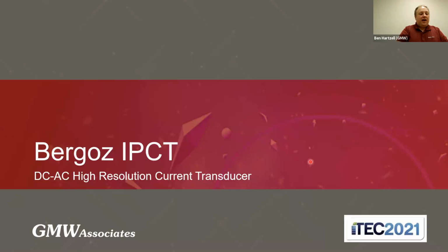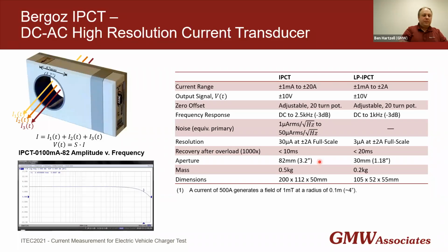Next, we have the Bergoz IPCT. The Bergoz IPCT is very similar to Danisense in operating principle. It's also a DC-AC zero-flux fluxgate current transducer, but there are several key differences in the specifications. It's very high resolution. You can see here 30 microamps on a 2-amp full scale. So you can also see that the scale is much lower than the Danisense was, but very high resolution.